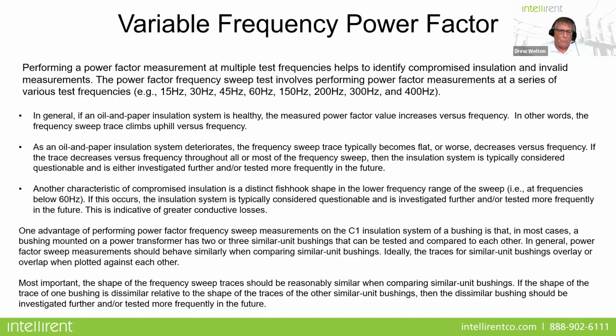But another characteristic that we see that's very distinctive is what we call the fish hook. And that is when your 1 or 10 to 60 hertz power factor measurements show a much higher value. What that's indicative of is what we call conductive losses. Now, what is a conductive loss? Well, in a power transformer, an oil-filled transformer, it could be sludge, it could be furans, but for bushings and transformers as well, it could be moisture intrusion. So the shape of the frequency sweep traces between all your bushings should be reasonably similar when comparing similar unit bushings. If the shape of the trace of one bushing is dissimilar relative to the other, then that dissimilarity should be considered something that needs to be investigated further.